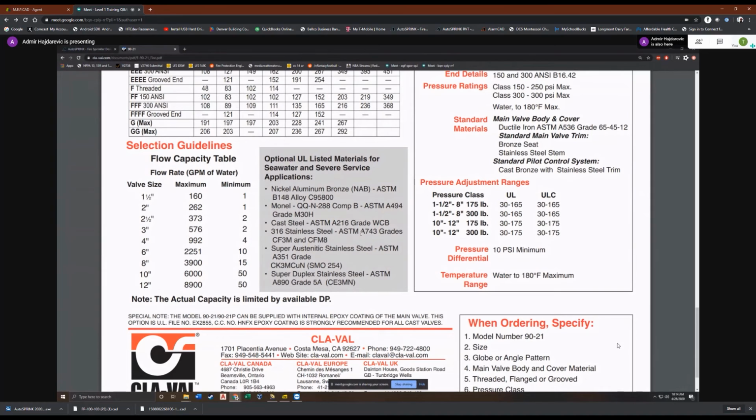Yeah, but it's a little tricky because you're running a demand calc, and PRVs function with consideration of acting pressure, not what's minimally required, but what's actually acting upon the valve and upon the system. Is that how the valve actually acts in AutoSPRINK? That's where it gets tricky, because in AutoSPRINK we're simply accounting for frictional resistance through the device to calculate the minimum required pressure and flow to satisfy that system flow demand. But in reality, that valve is going to have much more pressure acting upon it than what's required. So we have to account for the pressure loss through that valve based upon the actual acting pressure, not what's simply required.